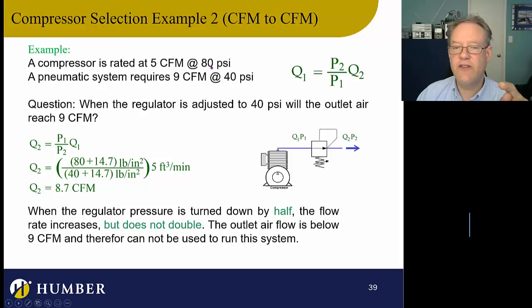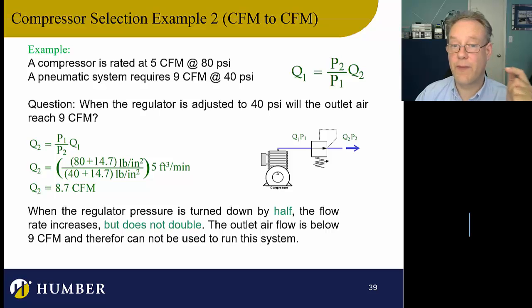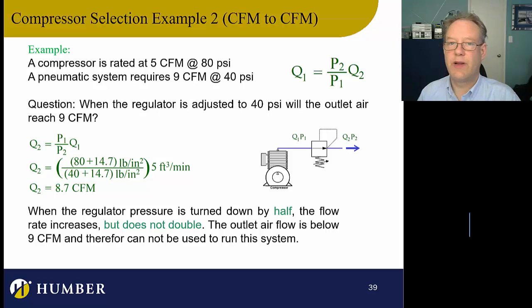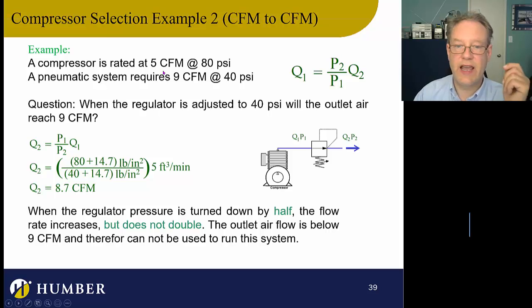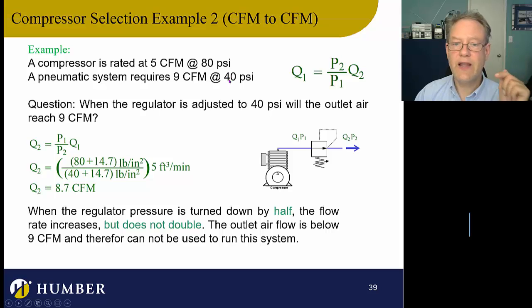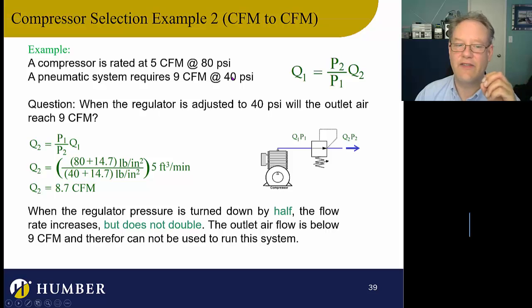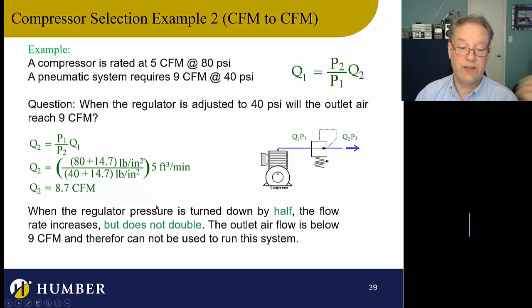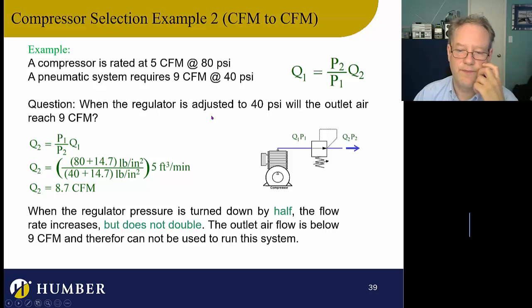It's pretty interesting — I've gone from 80 PSI gauge to 40 PSI gauge, which looks like halving the numbers, but that's not halving the actual pressure. In absolute terms it's 94.7 and 54.7, which is not half. That's why the flow rate doesn't double to 10 CFM — and why I'm not getting all the way to 9 CFM either.